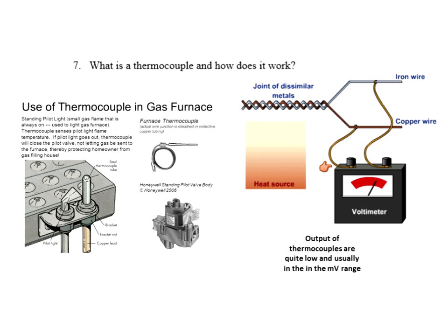You light the pilot, and then this thermocouple gets hot enough to generate a voltage to make a control system hold the valve open. That's why we use thermocouples. That's a really good spot for it—gas furnace, gas water heater. It's used to indicate there is a flame there, a flame that will ignite the large burner whenever that burner turns on. If there's no flame there and that burner turns on, you're really going to fill your cellar or area with natural gas. So that's what a thermocouple is.